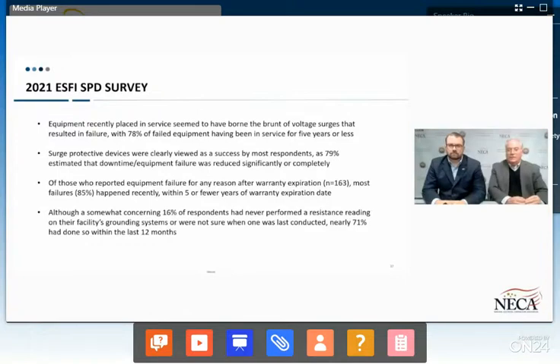If I can add to Keith's response, which was spot on—I'll talk more about this when we discuss the timeline and how the NEC is evolving—but a lot of the equipment being installed by contractors today, used in essential electrical systems and emergency systems, has integrated electronics as part of it. Fire pumps are another example. When equipment needs to be resilient and maintain continuity of service, surge protective devices are directly related to that equipment remaining operational.